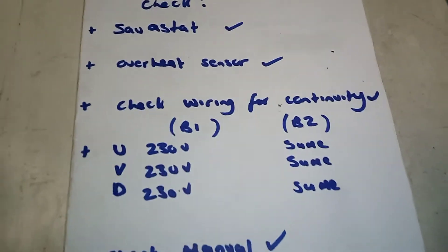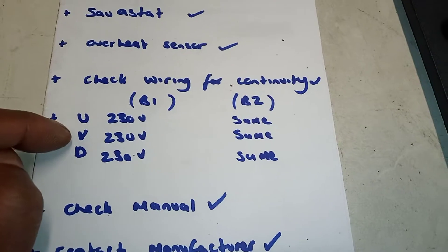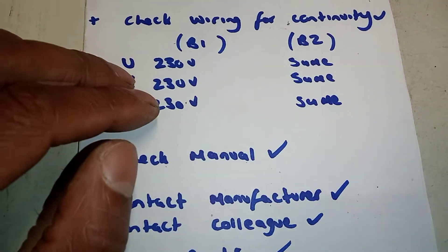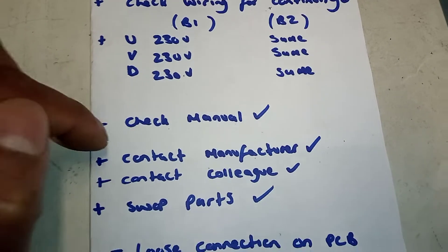I then checked my wiring on the U, V and D — there's the U, V and D — and checked my wiring to make sure I was getting the same calls from boiler one, the good boiler, as from boiler two, the bad boiler. I was checking I was getting the same calls for heat, and all looked well there.